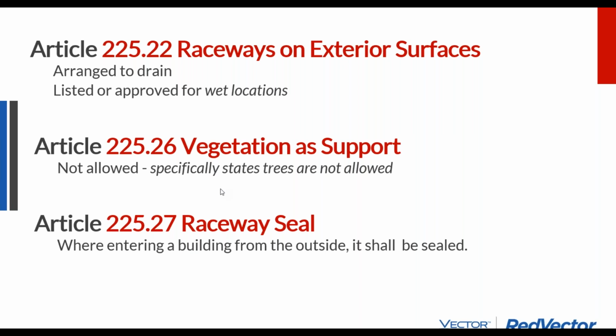This is a good one, the raceway seal. When you're entering a building from the outside, you have to seal the inside of the conduit, because the air between the inside and the outside has a temperature differential, and that can cause condensation and moisture inside of your conduit. That's true from any temperature differential, from underground to above ground, and also from going from the top of the roof into the building.